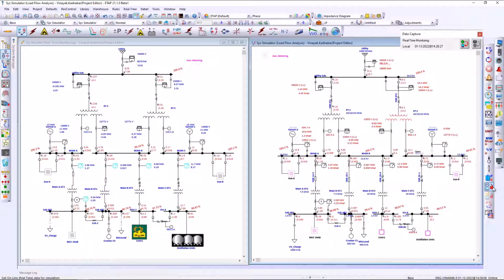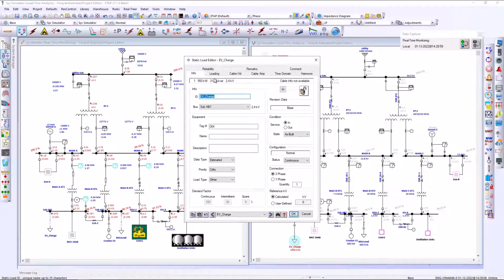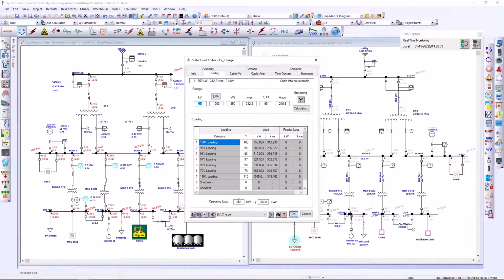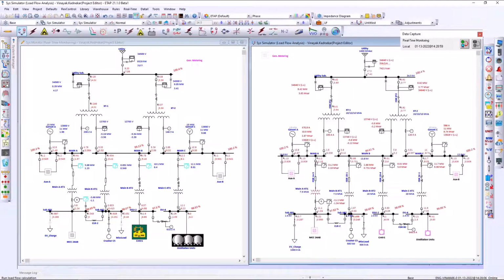Another example is, in this model, there is a group of loads modeled on my ETAP model, and the current planning schedule will require to increase the load. Before taking this action, I can evaluate the scheduled amount of load on the bus, run the simulation, evaluate the results. As you can see from the scenario results, increasing this amount of load will certainly cause an overload in one of my transformers.